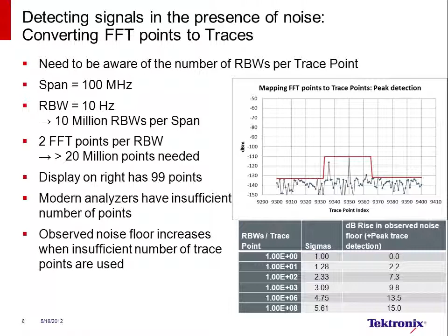In the table at the bottom right of the page, note that as the ratio of the RBWs to trace points increases, the reported dB rise in observed noise floor increases. This is based on the number of standard deviations that would be present with a plus peak detection when measuring noise with a Gaussian distribution. Those last few slides talked about issues to be concerned about when performing measurements of signals in the presence of noise, or signals that are close to the noise floor.